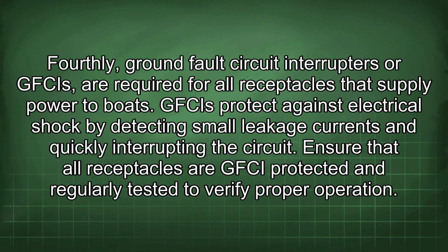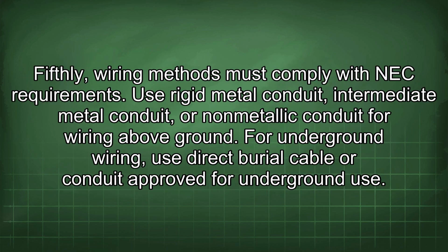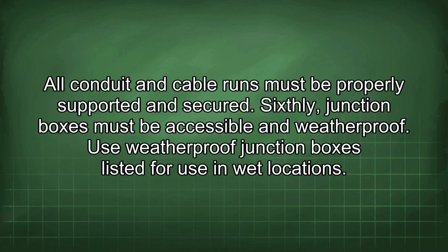Fourthly, ground fault circuit interrupters, or GFCIs, are required for all receptacles that supply power to boats. GFCIs protect against electrical shock by detecting small leakage currents and quickly interrupting the circuit. Ensure that all receptacles are GFCI protected and regularly tested to verify proper operation. Fifthly, wiring methods must comply with NEC requirements. Use rigid metal conduit, intermediate metal conduit, or non-metallic conduit for wiring above ground. For underground wiring, use direct burial cable or conduit approved for underground use. All conduit and cable runs must be properly supported and secured.